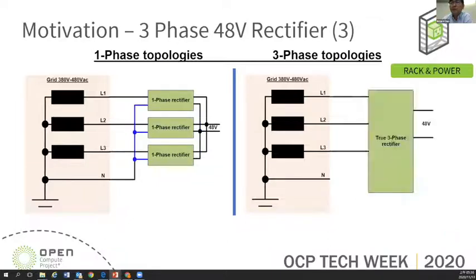Another interesting topic we learned from our customer is that if the current sharing is not good in the single phase approach, then there will be some current in the neutral wire. In the worst case, if the neutral winding impedance is big, that may impact the power system stability. However, if we do the 3-phase design, since we don't have the neutral winding, we don't need to consider this kind of unbalance, which could cause a power stability issue.